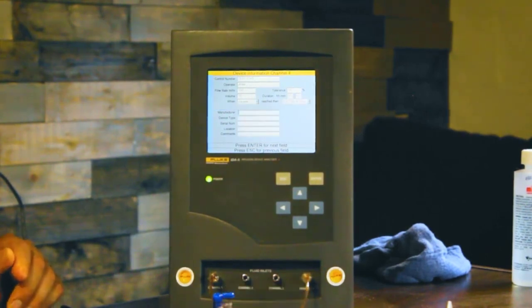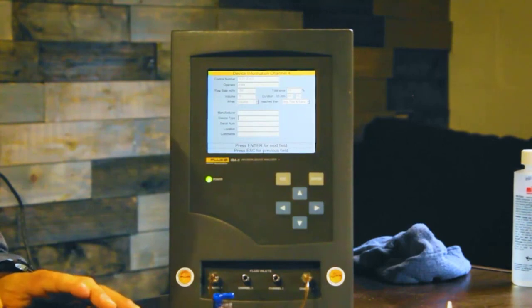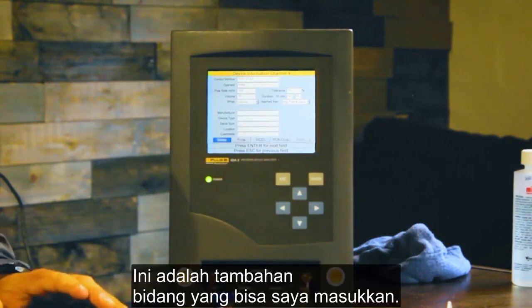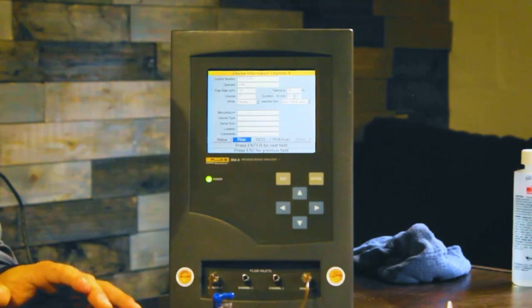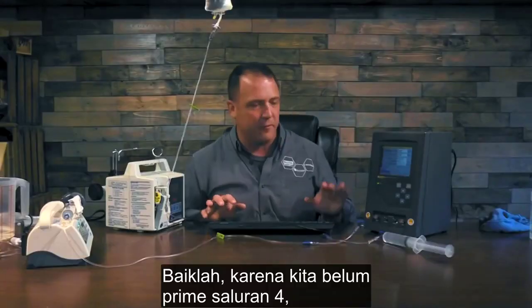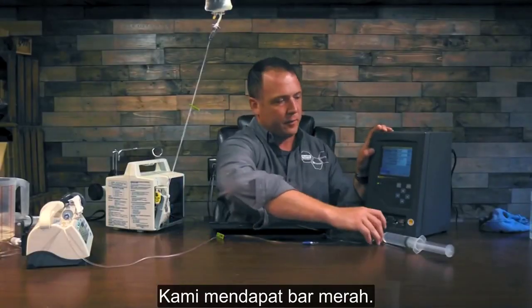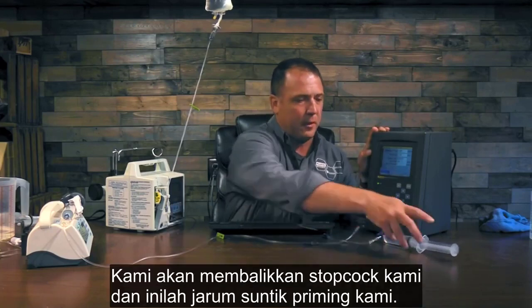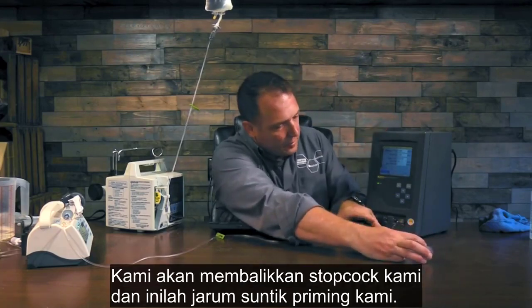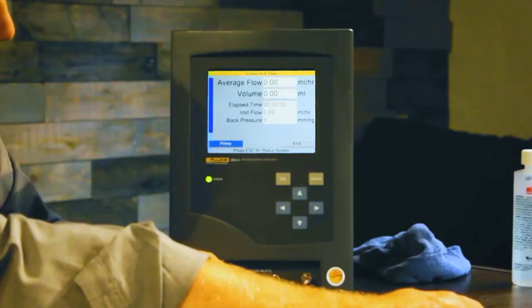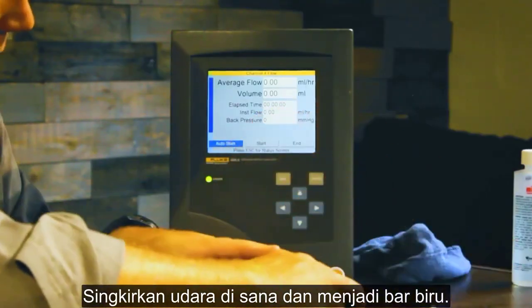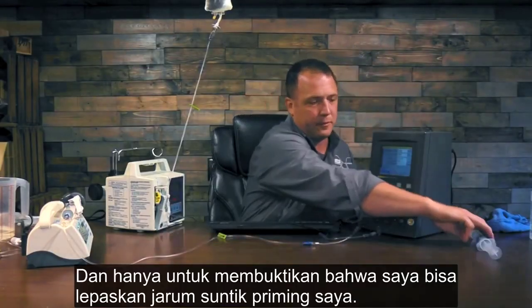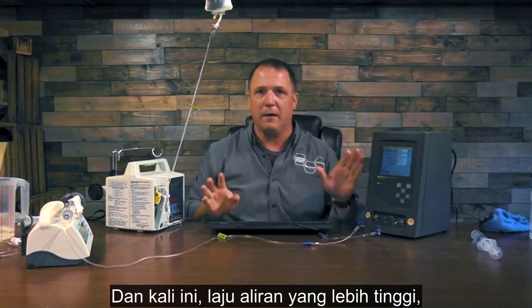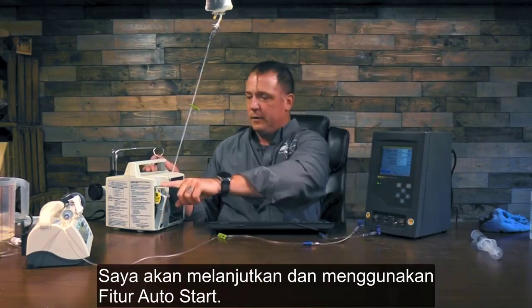And more. Nope. These are additional fields I can enter in. And now let's go to flow. Alright, since we haven't primed channel 4 yet, here we are. We've got a red bar. We'll turn our stopcock over and use our priming syringe. Get rid of any air there, and the blue bar. Alright, and just to prove, I can take my priming syringe off. And this time, higher flow rate, I'm going to go ahead and use the auto start feature. So let's get our infusion pump ready to go.